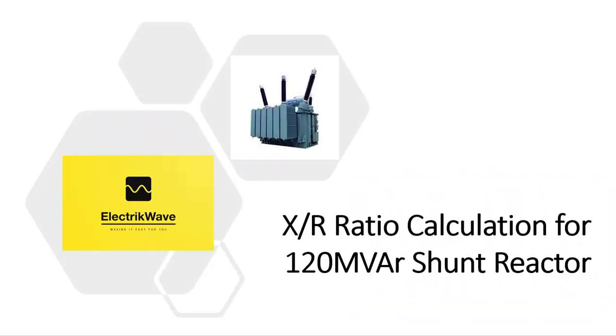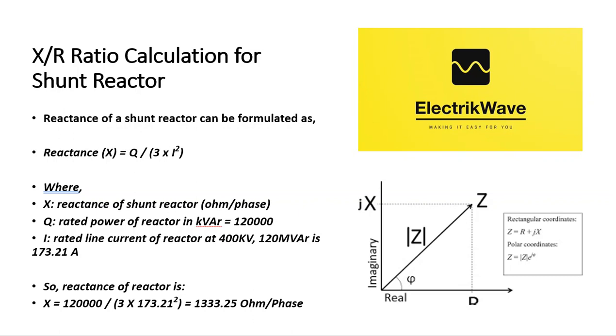Now let's discuss the X by R ratio calculation for a 120 MVAR, 400 kV shunt reactor. Reactance of a shunt reactor can be formulated as X equals Q divided by 3 times I squared, where X is reactance in ohm per phase, Q is rated power of reactor in kVAr (120,000 kVAr), and I is rated line current at 400 kV, 120 MVAR, which is 173.21 A. So reactance of reactor X equals 120,000 divided by (3 × 173.21²) equals 1333.25 ohm per phase.